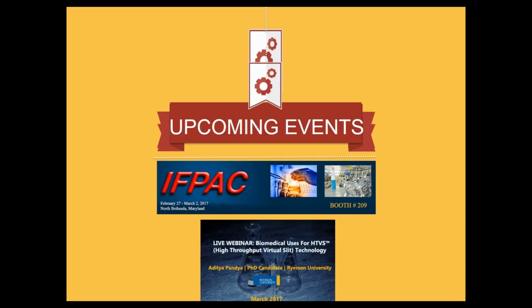The higher the level. And this is the inherent advantage of HTVS, by comparison to other dispersive designs. When they talk about the laser power creating that Raman excitation, maybe only 5% of the photons generated ultimately reach the detector. With HTVS, we actually invert that: we have maybe at most 4% loss reaching the detector via HTVS. So 96% of the total photons generated by the sample reach the detector. If you're in a counting situation, you get there much faster, with photons hitting at a much higher order of magnitude within a given time. So first we determine the signal strength.